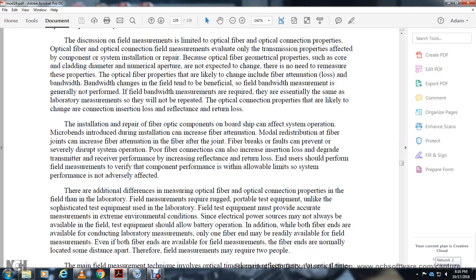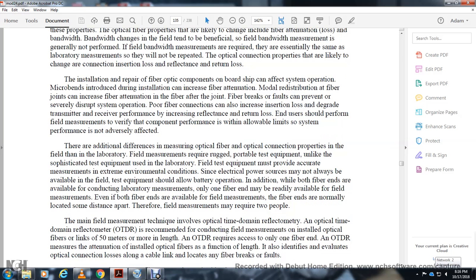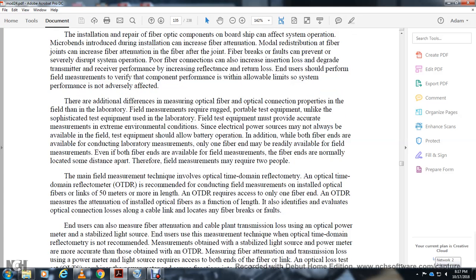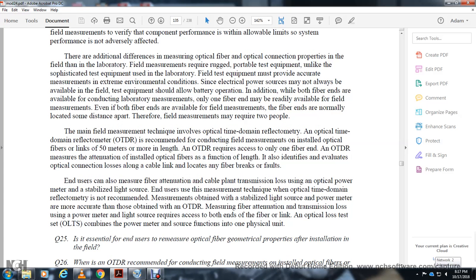End users should perform field measurements to verify performance within allowable limits. Field test equipment must be rugged, accurate, and battery-operated to handle extreme environmental conditions. Unlike laboratory setups where additional fiber ends are easily available, field measurements may have limited fiber access and may require two people. The main field measurement technique for optical fiber is the optical time domain reflectometer (OTDR), which is recommended for installed optical fiber of 50 meters or more in length.